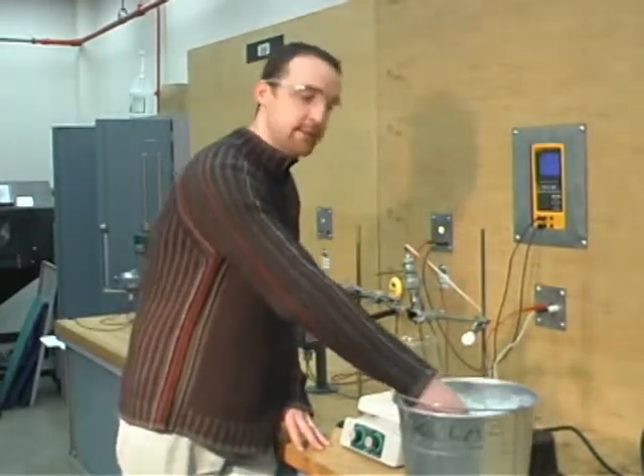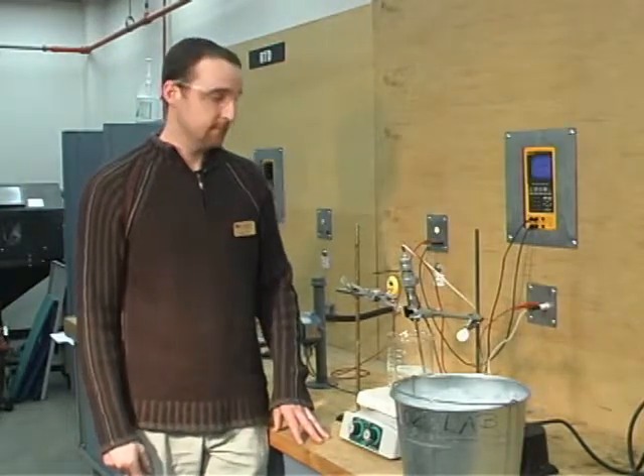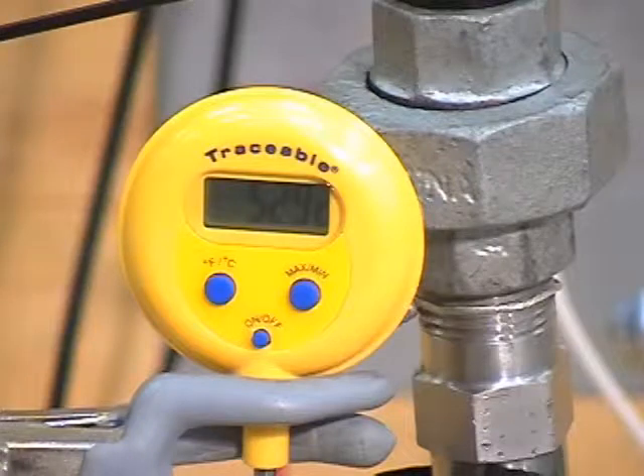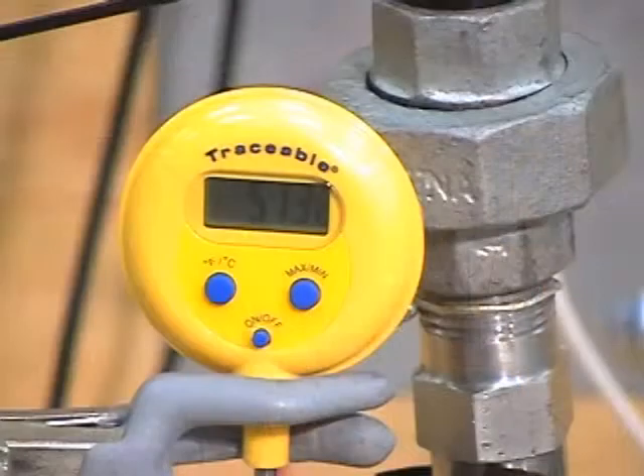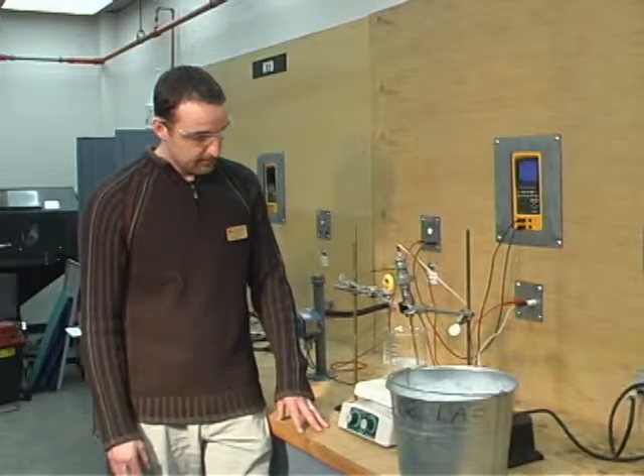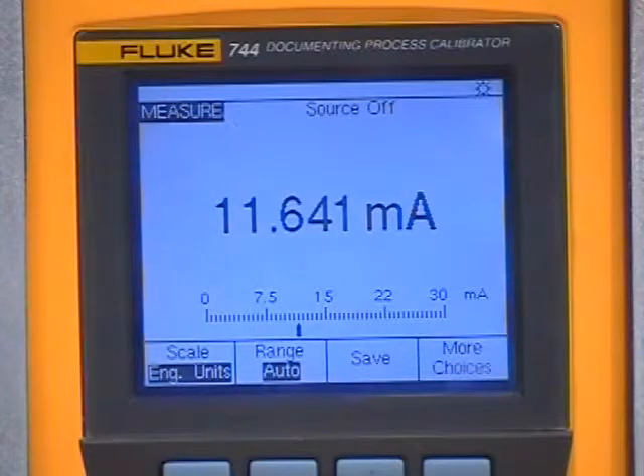Now down to our halfway point of 50 degrees Celsius. At this point, we should see roughly 12 milliamps. At 50 degrees Celsius, we are reading 11.95 milliamps.